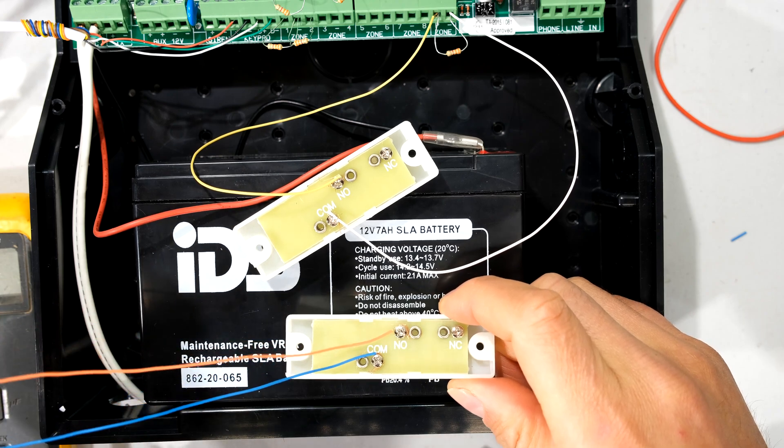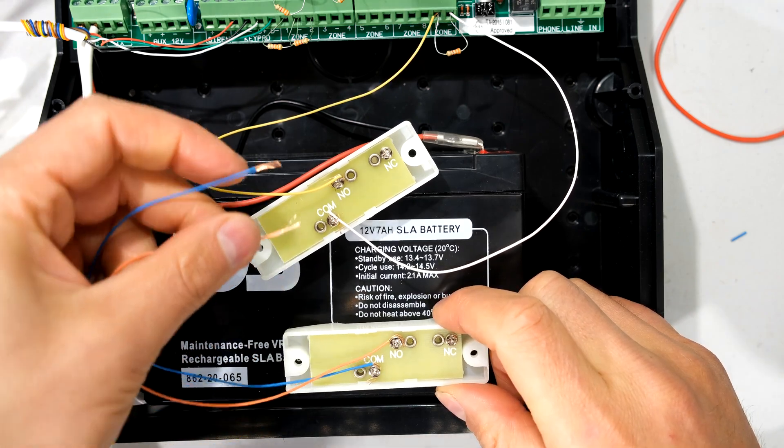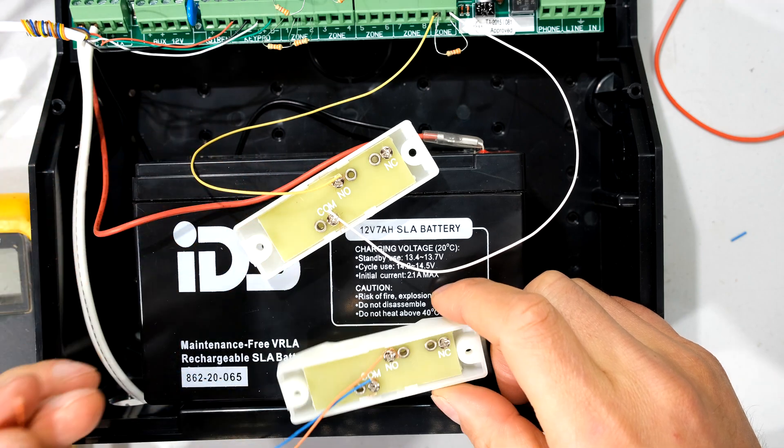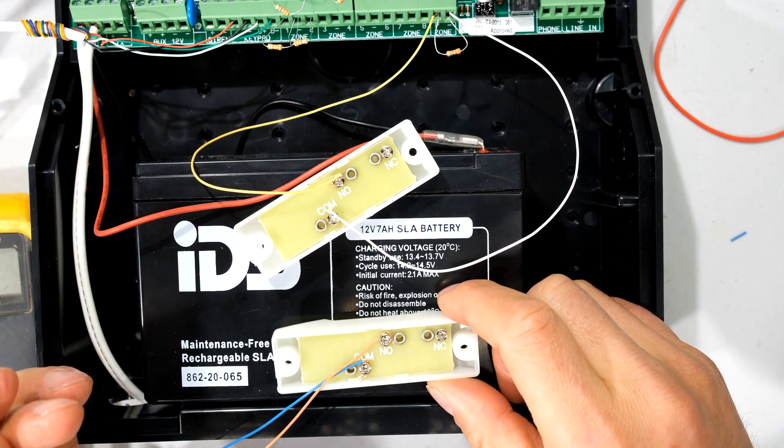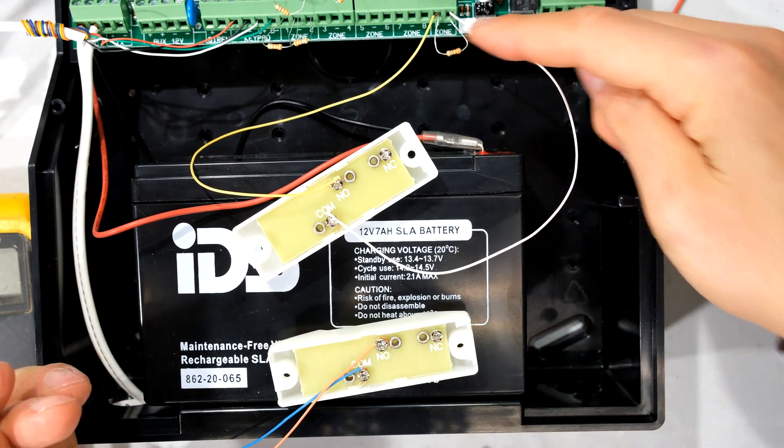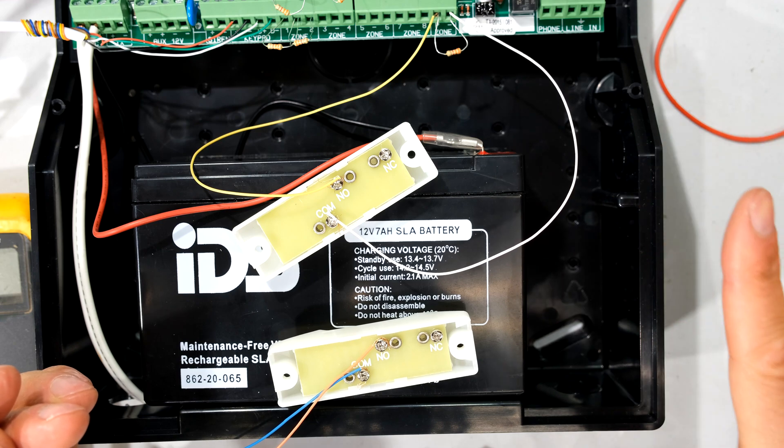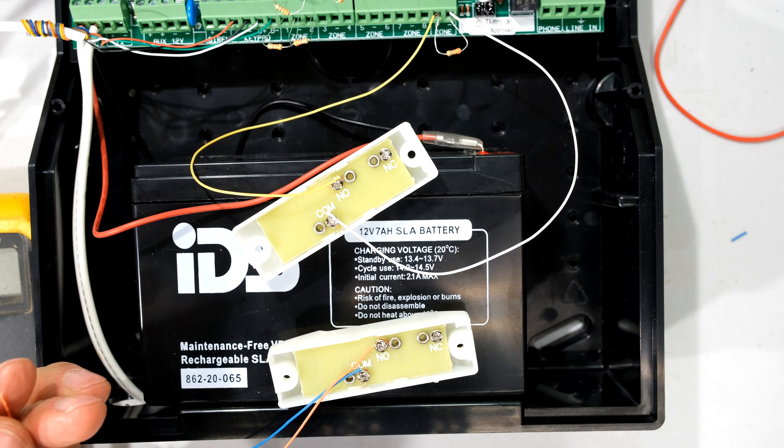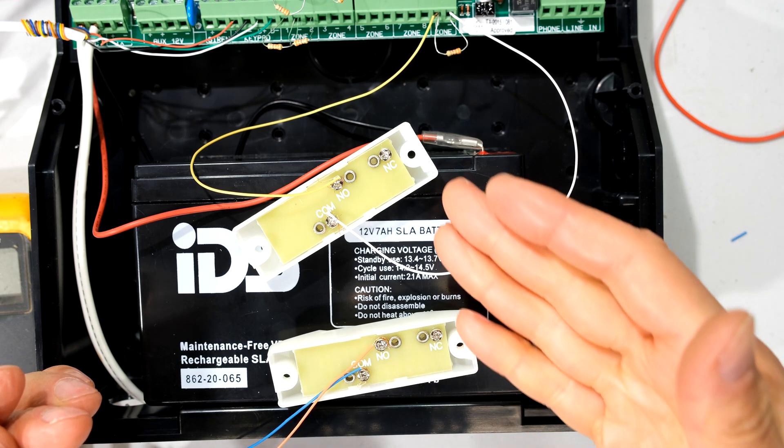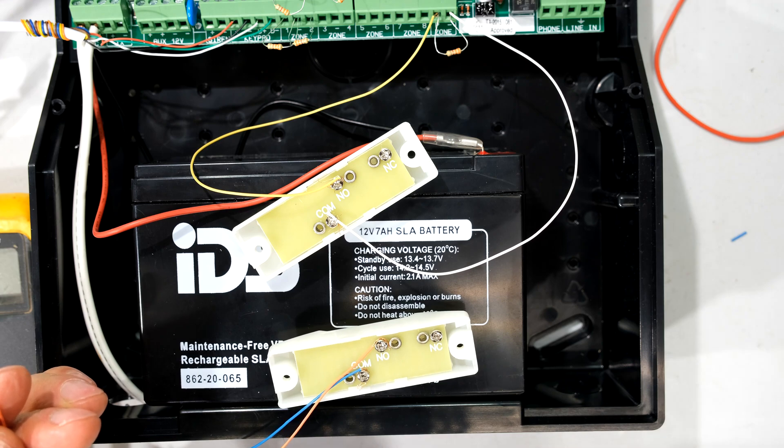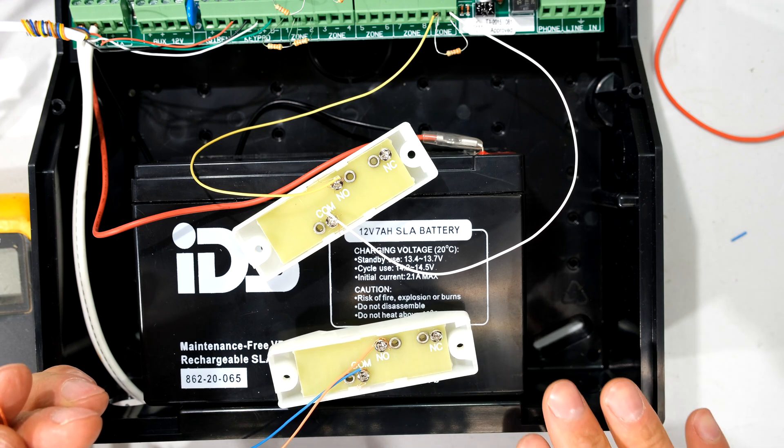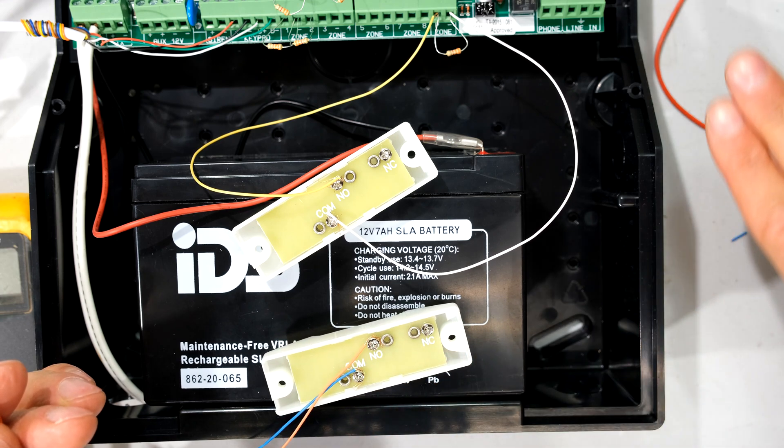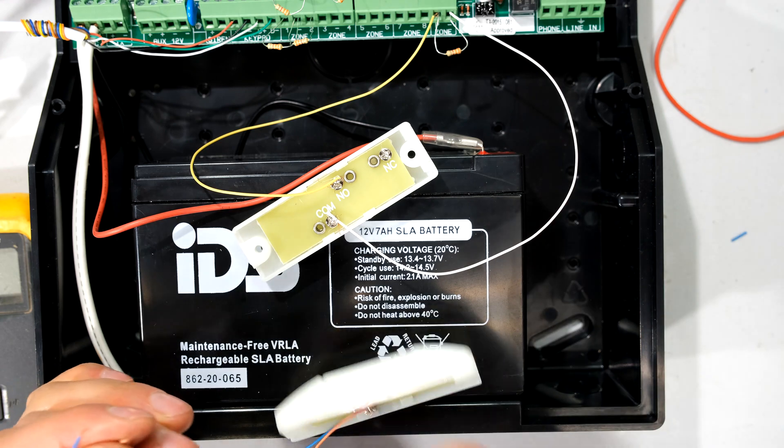You could daisy chain them like that. But because it's a panic button I prefer to run it directly to the panel. If a cable gets cut or something like that and then people have not tested their panic buttons they will then have many panic buttons which don't work. So when it comes to panic buttons I actually run them directly all the way back to the panel.